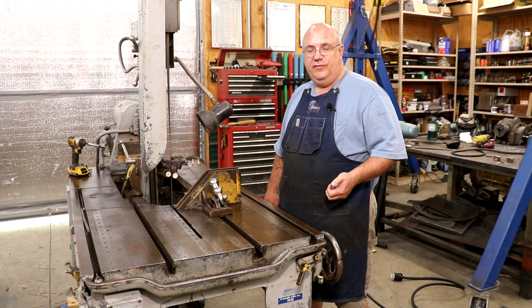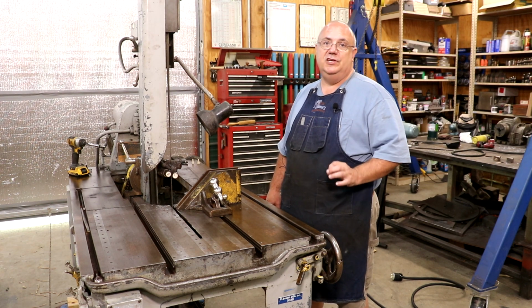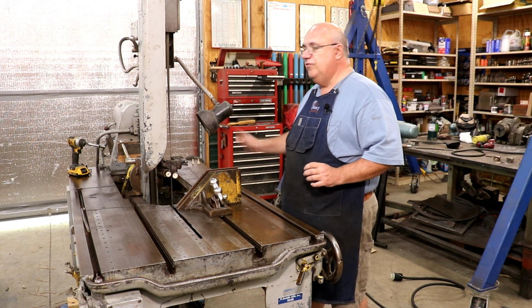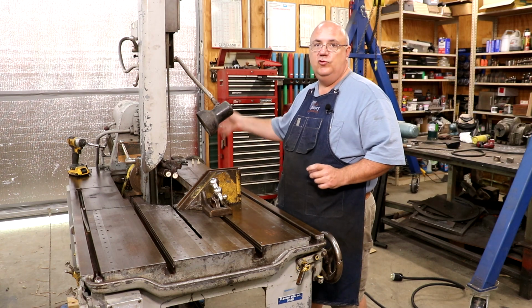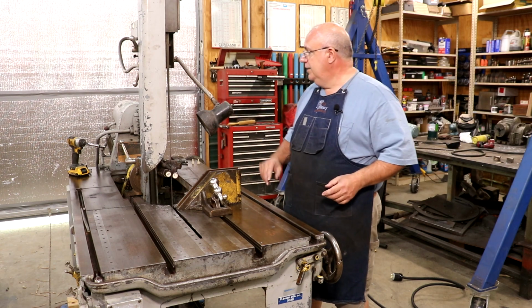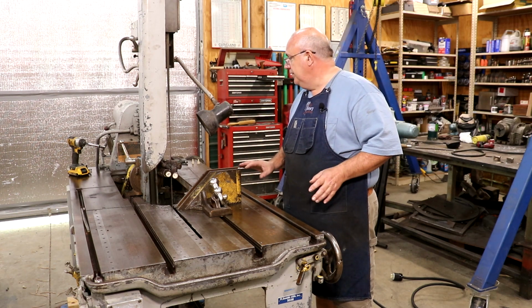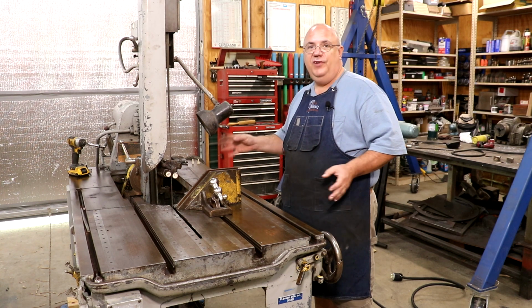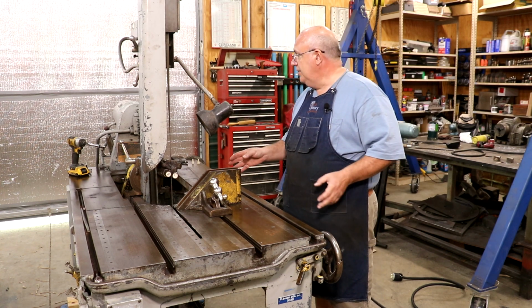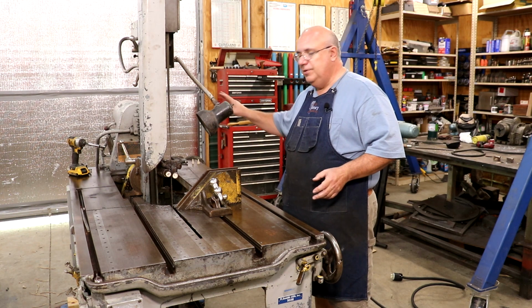On the electrical stuff, you saw the process of switching a motor over from 440, 480 volts to 220, 240 volts, or whatever voltage you're on in your particular location. Fairly straightforward, nothing too crazy, but it does require a little bit of things you need to do.